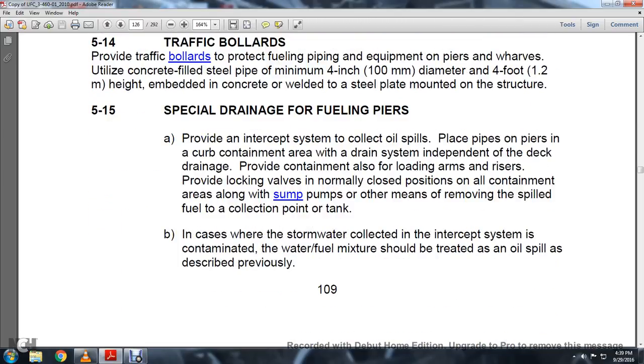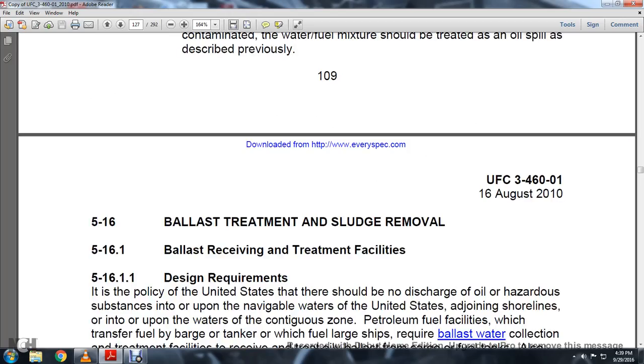515 special drainage for the fueling piers. Provide an interception system to collect oil spills, placing the pipe at the piers with curbed containment, with a drain system independent of the deck drainage. Provide containment also at the loading arm risers. Provide locking valves, normally in the closed position, on all containment areas, along with sump pumps and other means of moving the spilled fuel to a collection point or tank. In this case, the stormwater collected with the interception system is a contaminated water-fuel mixture and should be treated as an oil spill as directed previously.